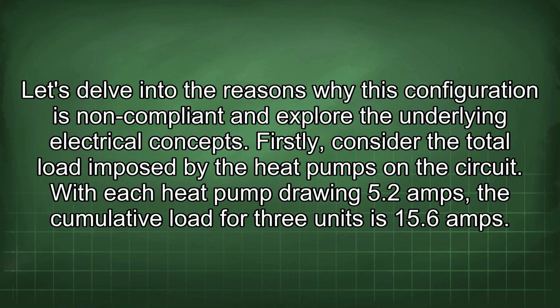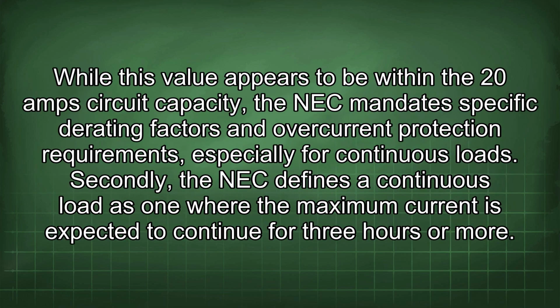Firstly, consider the total load imposed by the heat pumps on the circuit. With each heat pump drawing 5.2 amps, the cumulative load for 3 units is 15.6 amps. While this value appears to be within the 20 amp circuit capacity, the NEC mandates specific derating factors and overcurrent protection requirements, especially for continuous loads.